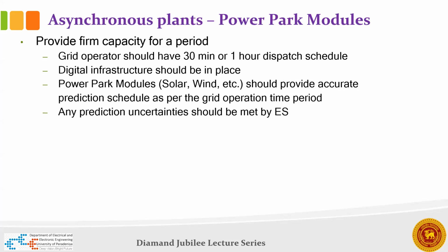Prediction uncertainties can be met by small energy storage. You don't need huge storage if you're firm up to 95% for that time period - the remaining 5% comes from energy storage. The capex for market or control operations is met by the grid operator, but capex for providing accurate predictions and sending them on time has to be borne by the power park module.